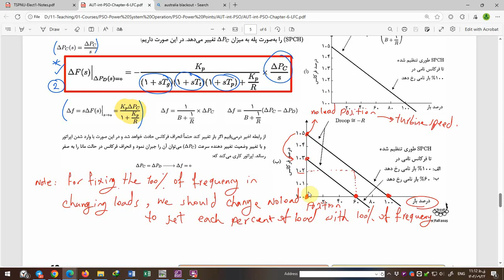After that, we introduce how we can compensate when the percent of load is decreased from 100 to 60%, and you have to decrease this point. This point is the no load position, and the no load position is affected by the turbine speed, and you can change the no load position for any percent of load at 100% of frequency.